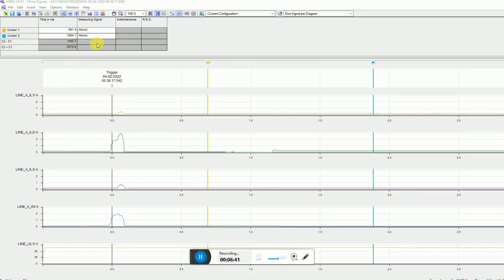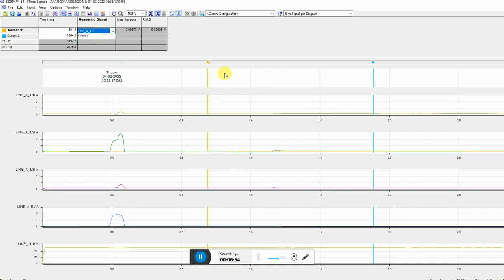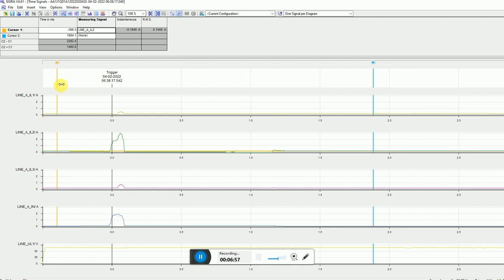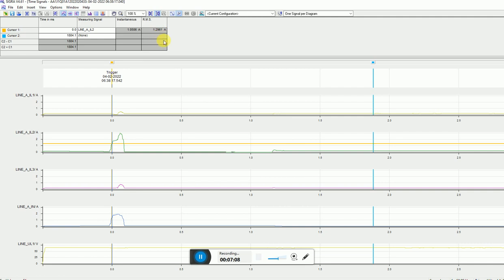What about the analog channel, there is no issue. We will see what are the values of current. You can see this is the current in Y phase. The current got suddenly high, then it is low. We will see what is the value of Y phase current before the fault was there. You can see here, this is the value of 0.141, means 140 ampere. When there is a fault, suddenly the value increases to 1.29 kiloampere, means there is a fault in Y phase of the transmission line.